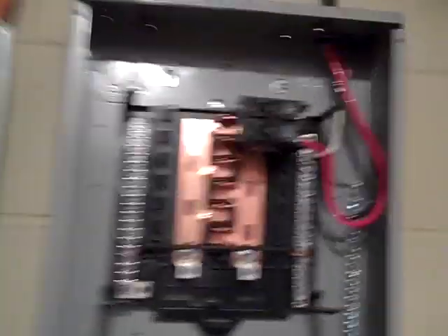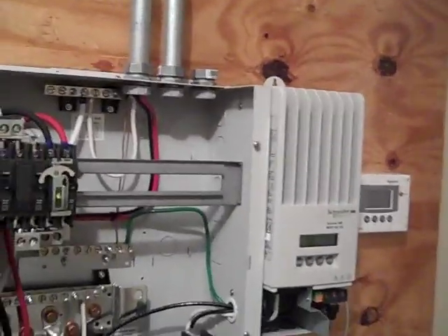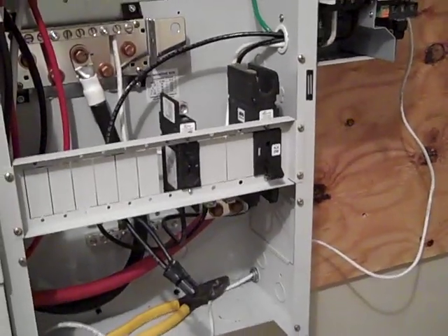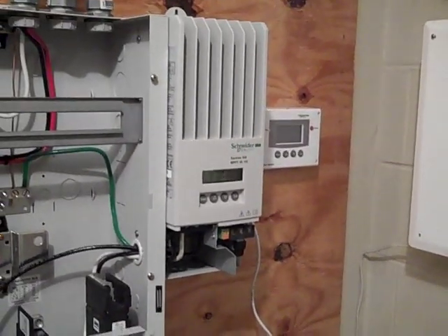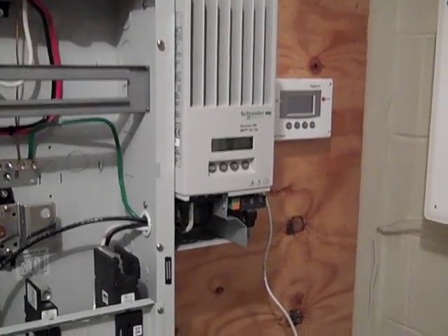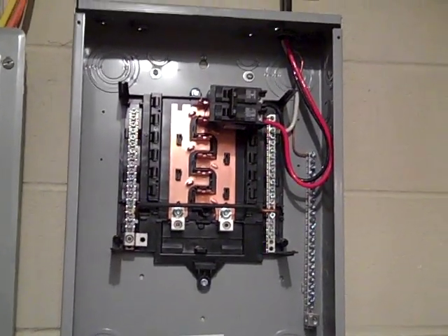We just mounted the secure panel and put a double 60-amp breaker in that's coming from the distribution panel. We've wired up some of the charge controller — this is an MPPT 60 150, so the solar panels on the roof are in groups of three in series to stay under 150 volts per string. There will be four strings on the roof — 12 panels, four strings — coming into this charge controller, which controls the charging rate of the battery bank. We'll finish up pulling at least eight, possibly nine, critical circuits and rerouting them into the secure panel.